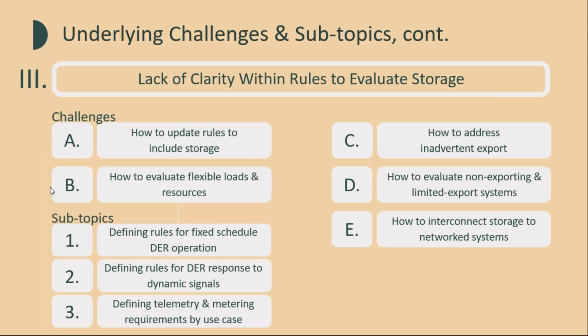For systems that are completely non-exporting, screening really doesn't need to include any detailed consideration of the amount of electricity the system exports to the grid. Another factor is whether there is a definition of what non-exporting means, and whether it means completely disallowing any level of export or recognizing that negligible amounts of inadvertent export can be managed without serious impacts to the grid. In both cases, we want to avoid an overly burdensome review process while addressing system reliability concerns.